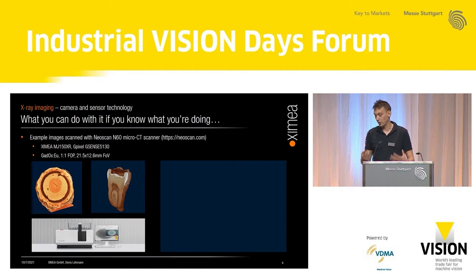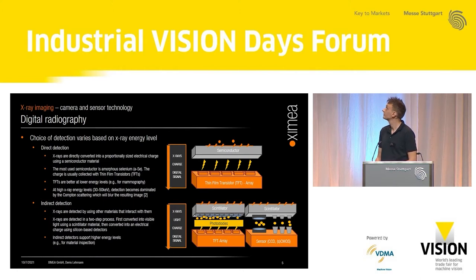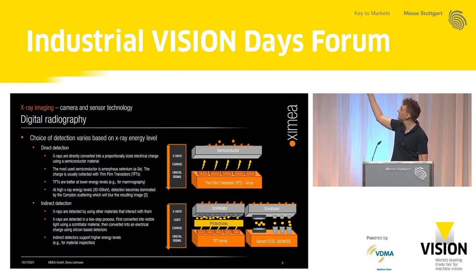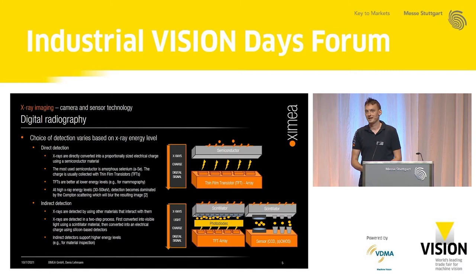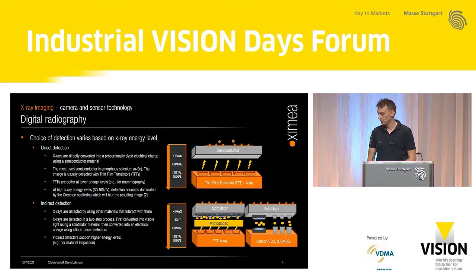Let's have a closer look at how detectors work. In general, there are two types of detection systems. First, there are direct detectors: they receive X-ray radiation and directly transform it into a proportionally sized charge, which is then given to a TFT array that converts it to a digital number. Direct detection is limited regarding energy levels — from my reading of papers, it's limited to around 30 to 50 kilo-electronvolts.